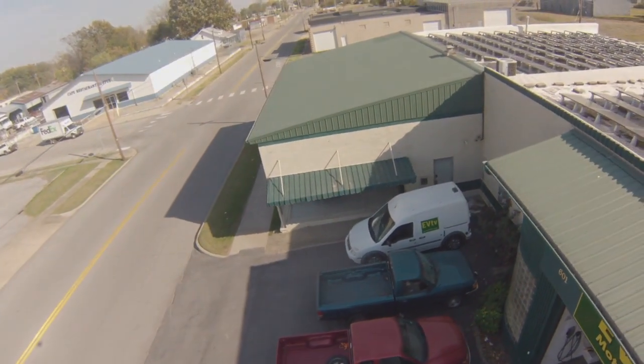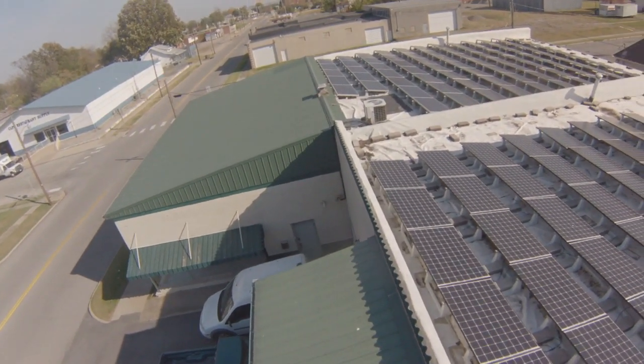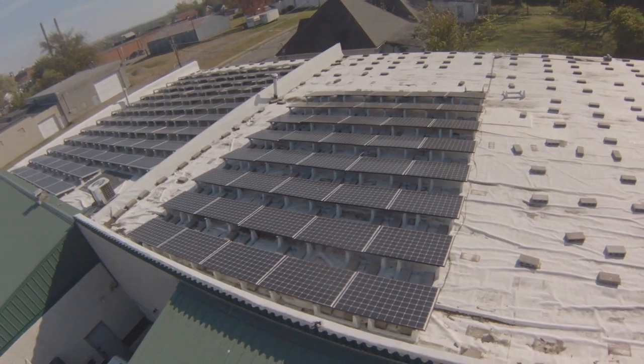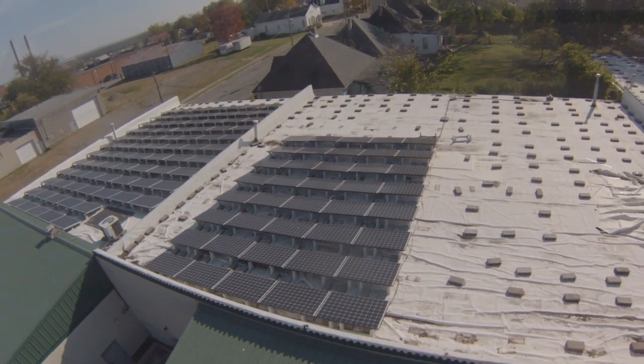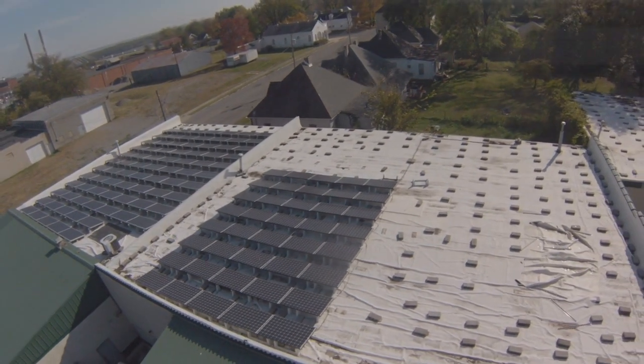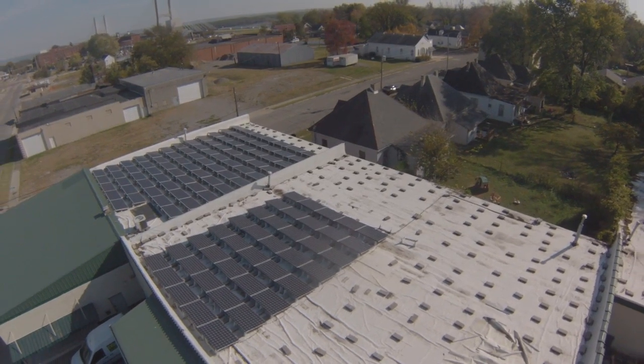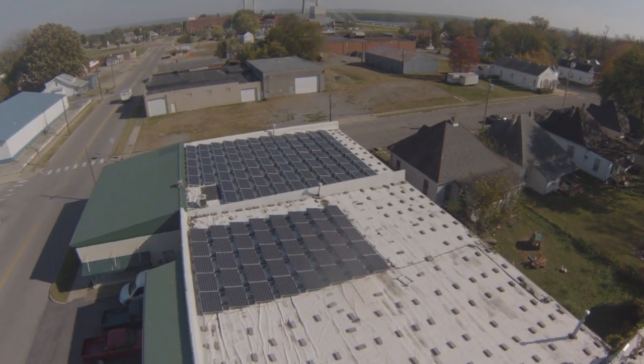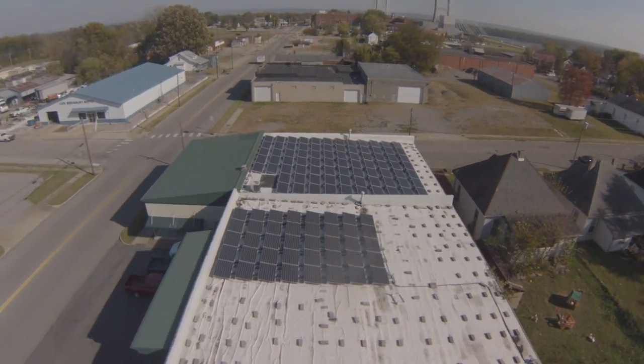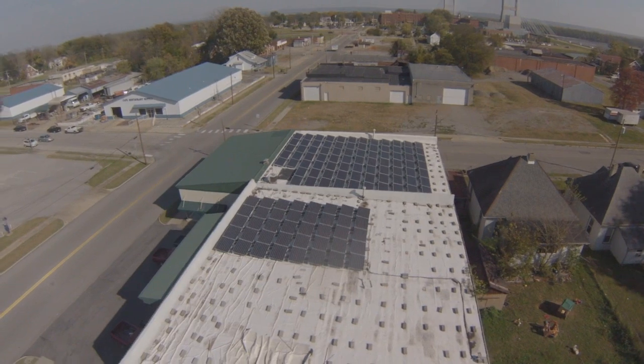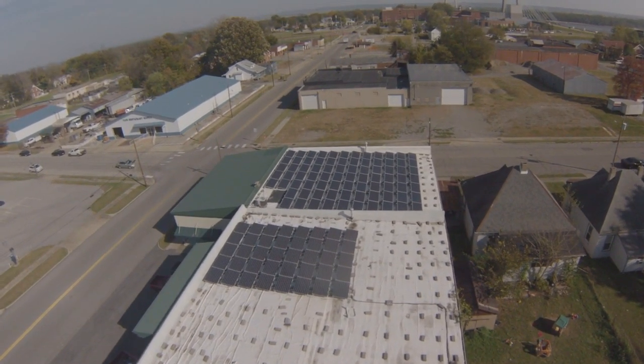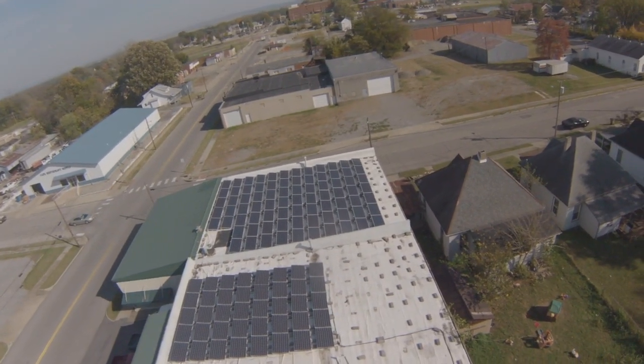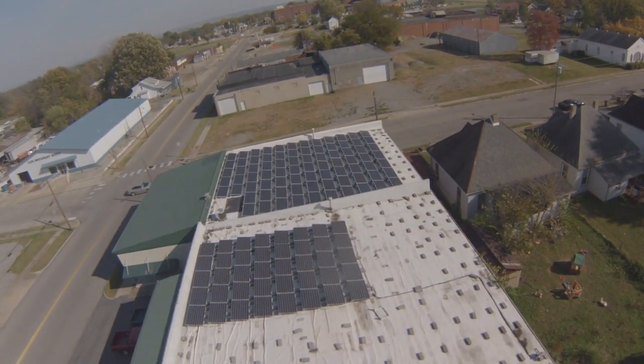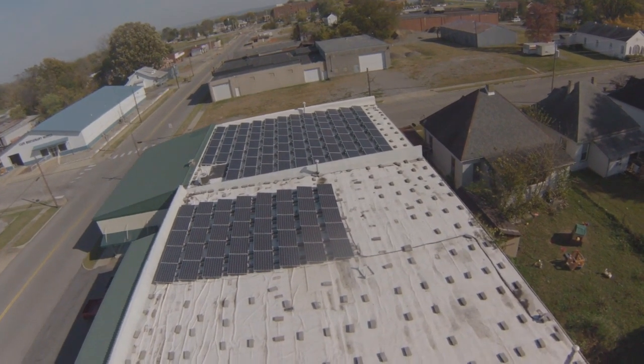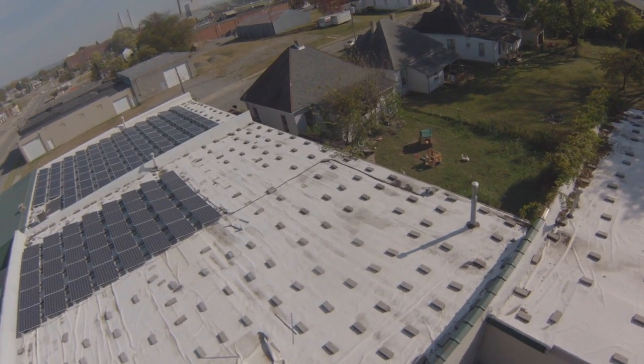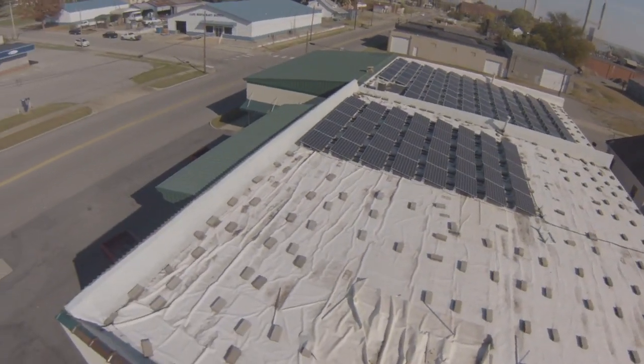Here we have a drone shot of our completed solar addition, 40 Panasonic HIT 315 watt panels. They're in five strings of eight panels each. Each string has an open circuit voltage of about 525 volts, 480 volts at 5.5 amps. And with five strings, that gives us about 27.5 amps, 13.5 kilowatts of power. You can see the cabling routed over to the edge of the roof where it goes through a coupler down through the roof and then a conduit down the wall to a new circuit breaker panel that we have installed to handle this.